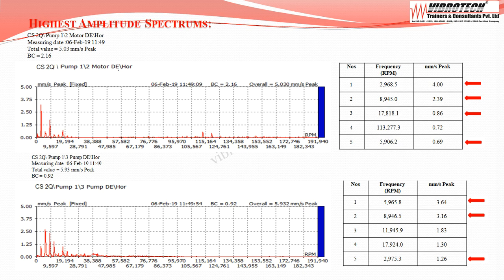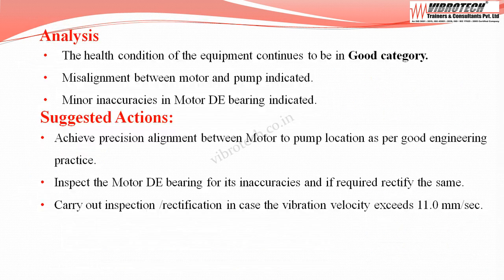Even though vibration levels are well within limits and the equipment falls under the good category, on going through the spectrum and frequencies at motor drive end, dominant peak frequencies of 1x, 3x, higher order frequencies, and 2x running RPM are observed, indicating bearing inaccuracies and misalignment between motor and pump. At the pump drive end, dominant peak frequencies of 2x, 3x, and 1x running RPM indicate misalignment between motor and pump. The equipment is analyzed to have misalignment and minor bearing inaccuracies at the motor drive end.